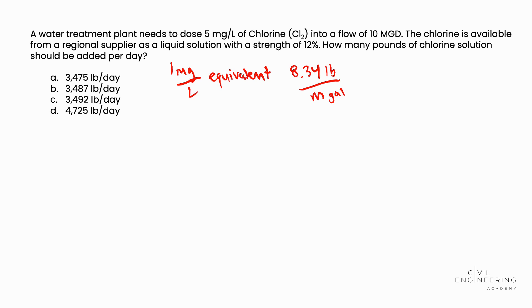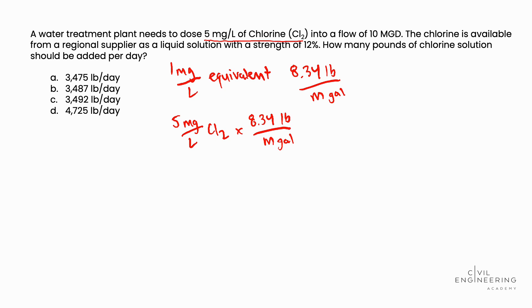Taking this knowledge, we then need to apply it to the problem. We're given 5 milligrams per liter of chlorine, so we take our 5 milligrams per liter of chlorine and multiply it by 8.34 pounds per million gallons — that conversion factor we just talked about. Then we multiply this by our flow. In the problem statement, we're given a flow rate of 10 million gallons per day, so we'll call that 10 MGAL per day.